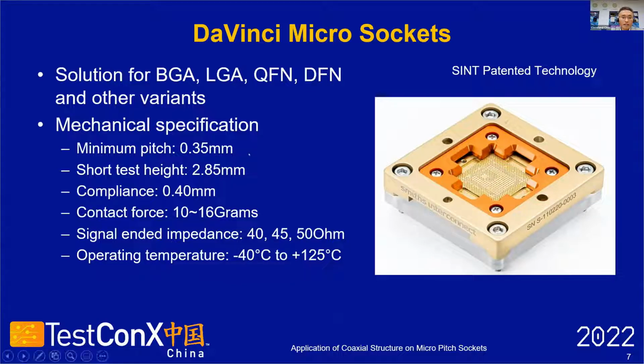Smith Interconnect overcame the above challenges and successfully developed the coaxial structure on a fine pitch device test socket, named DaVinci Micro, a new series of high-speed test sockets specifically for fine pitch device test applications. It is a proper solution for BGA, LGA, and QFN types of device testing.